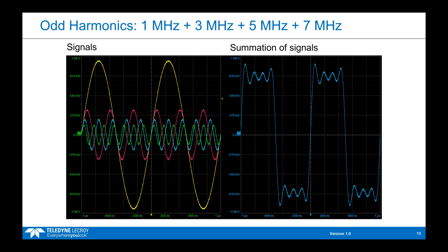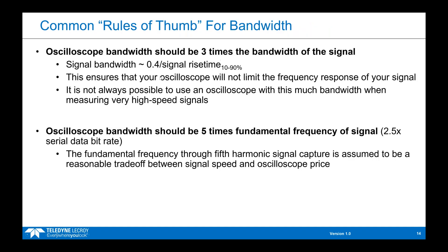You might be asking what are some rules of thumb for deciding exactly how much bandwidth you need. One rule of thumb states that you should obtain an oscilloscope with bandwidth that is three times the bandwidth of your signal, where signal bandwidth roughly follows the equation 0.4 divided by signal rise time. The takeaway is that ideally your oscilloscope's bandwidth is sufficiently higher than your signal bandwidth so the oscilloscope is not limiting the signal's frequency response.